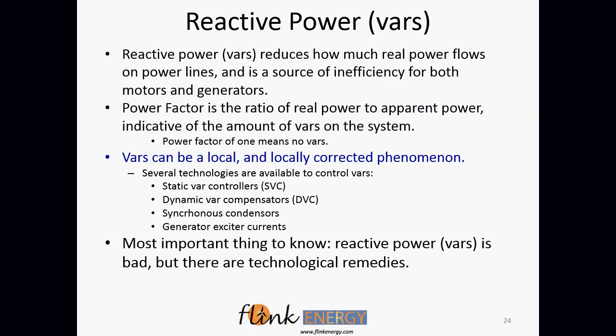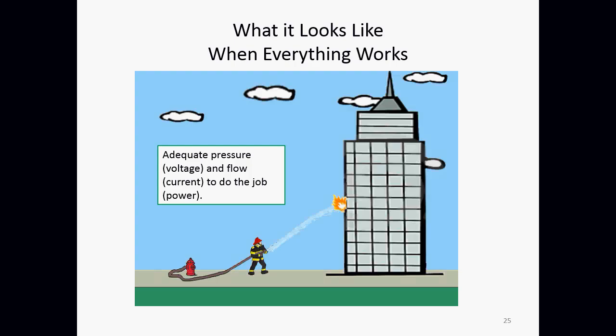The VAR problem can be local, and it's something that can be locally corrected, as I said, with capacitors. There are things called static VAR controllers, dynamic VAR compensators, synchronous condensers, which I talked about before, and they can also be adjusted with generator exciter currents. So the thing really to know about VARs is they can be problematic, but there are technological solutions to them. They cost something, but it doesn't cost a lot of energy, and it doesn't really cost a lot of money.